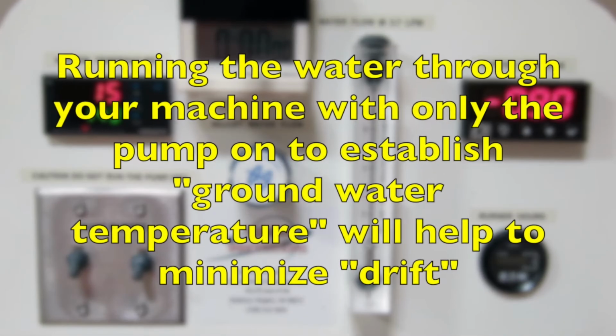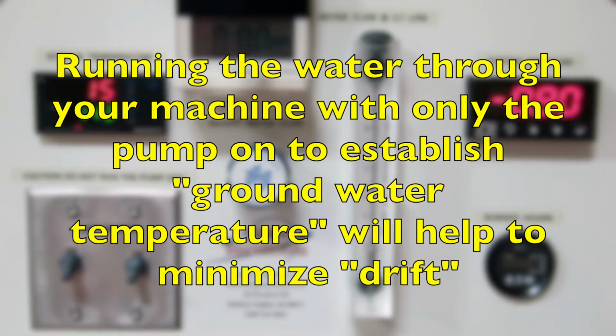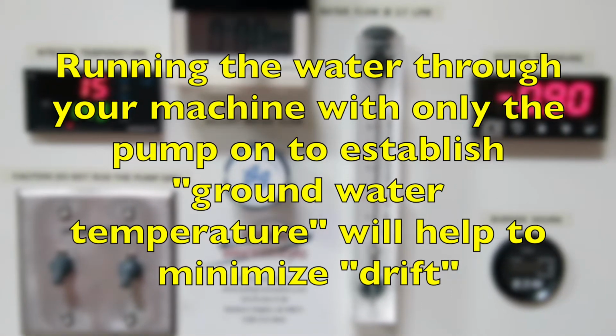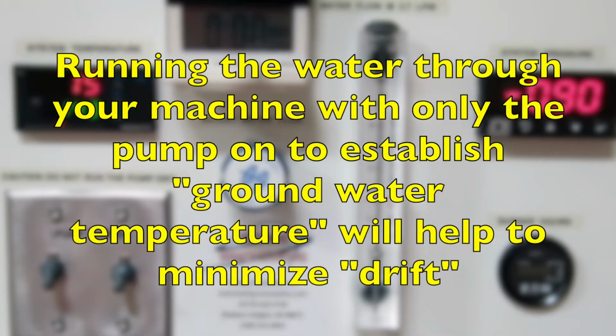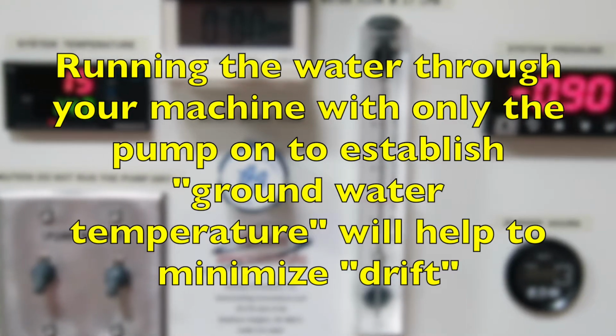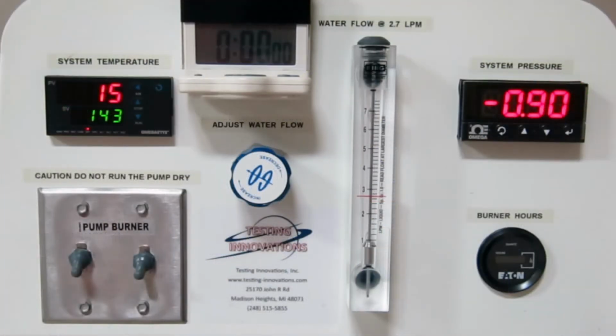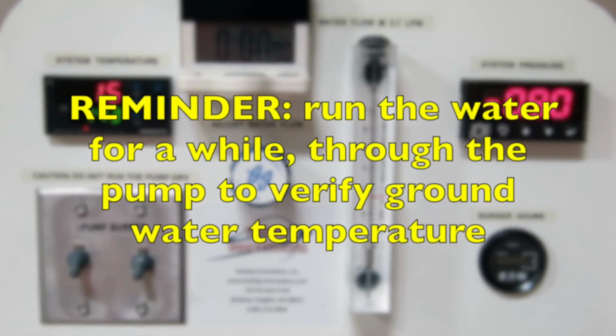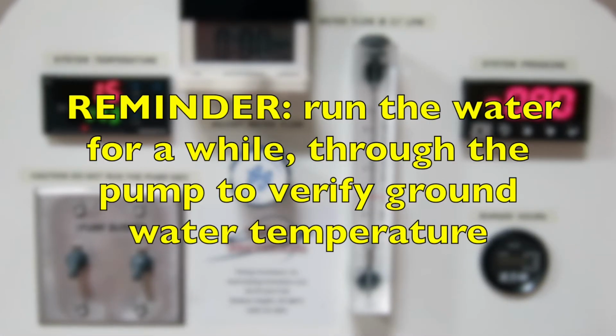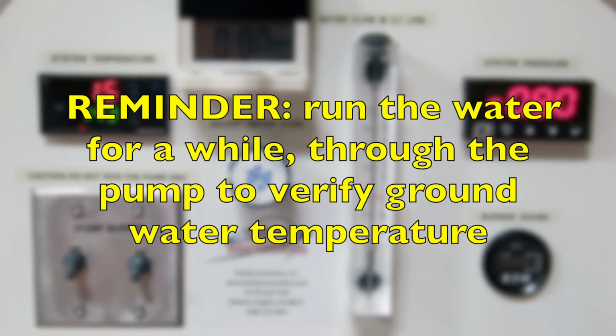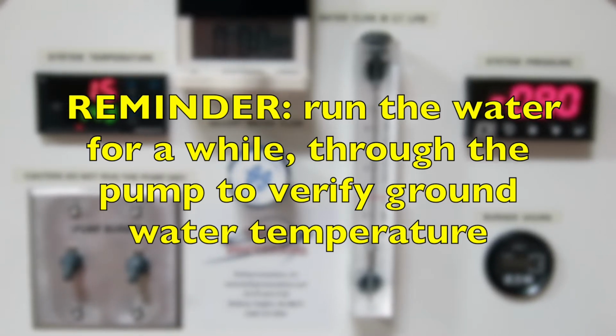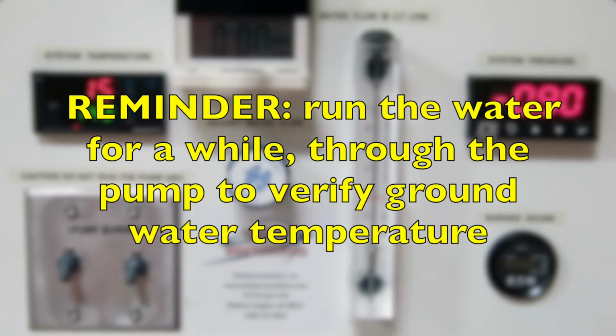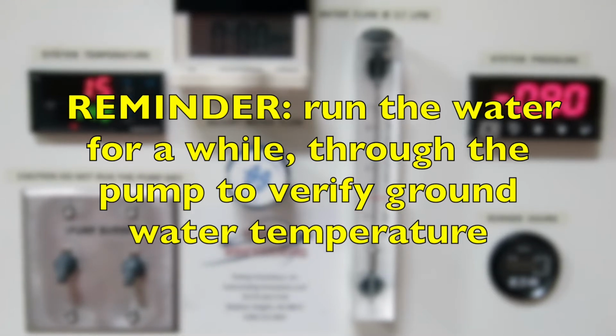You should run water through your machine with only the pump on for as long as it takes to find out what the groundwater temperature is in your area. The winter value is probably different than the summer value, so when you turn the pump switch on, you will be able to read the water temperature on the front panel temperature gauge in real time. So when you are ready to start a new testing session, do this before turning on the burner.